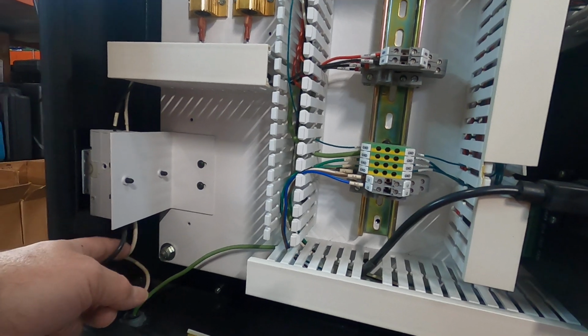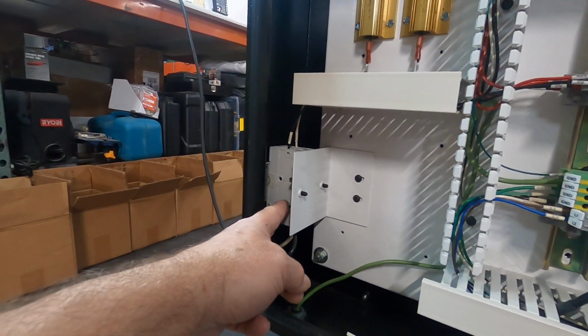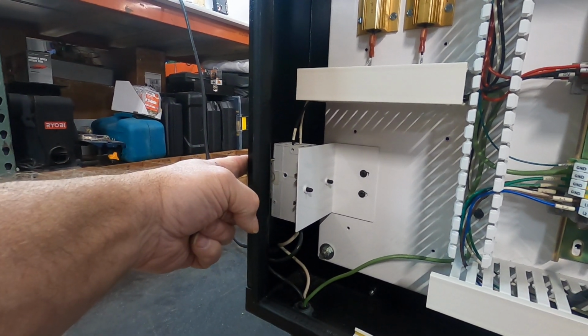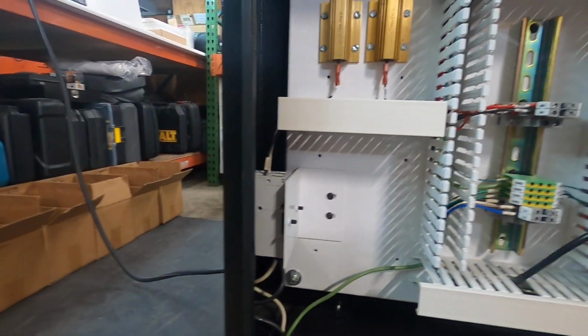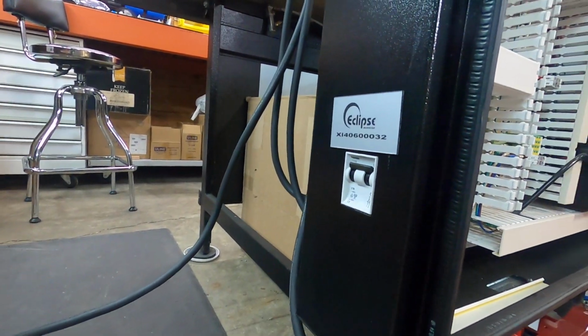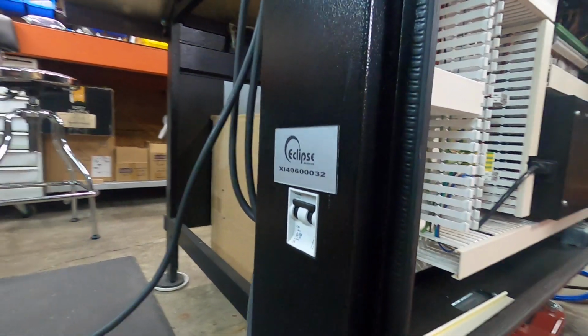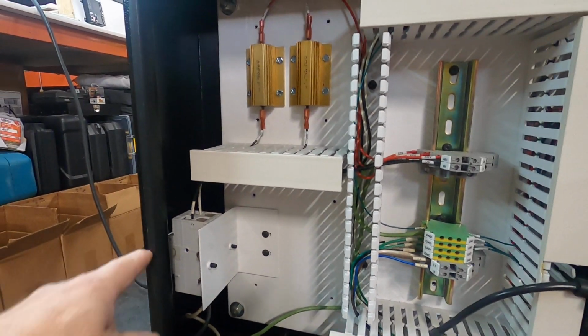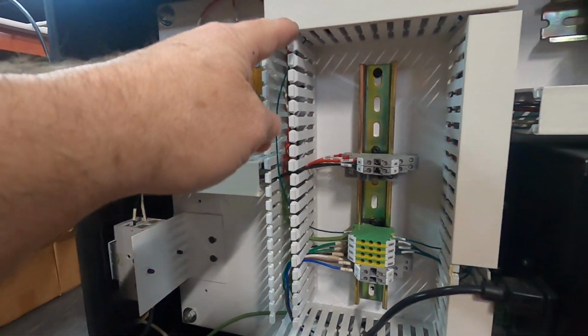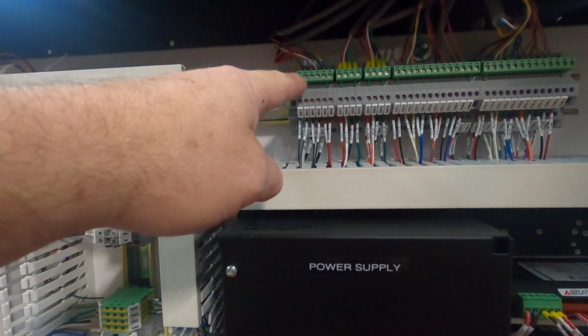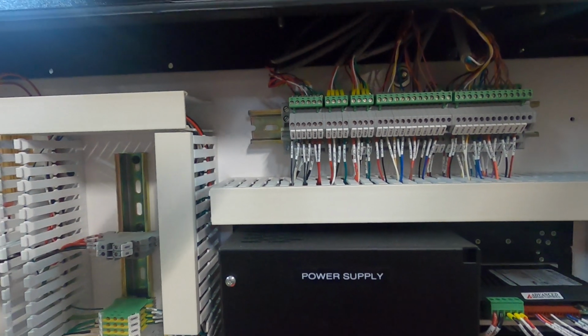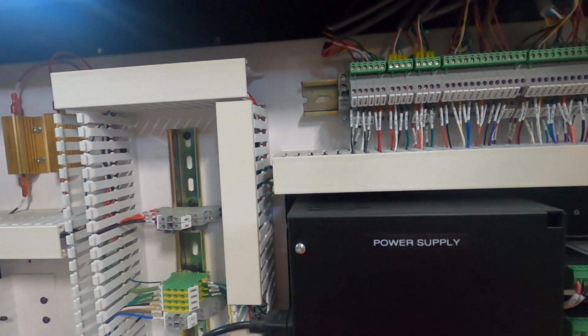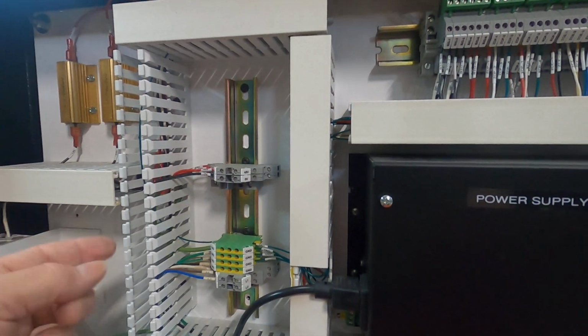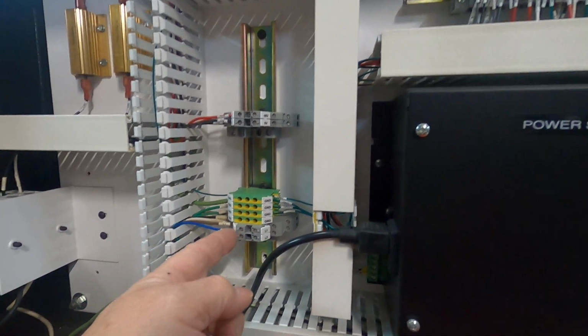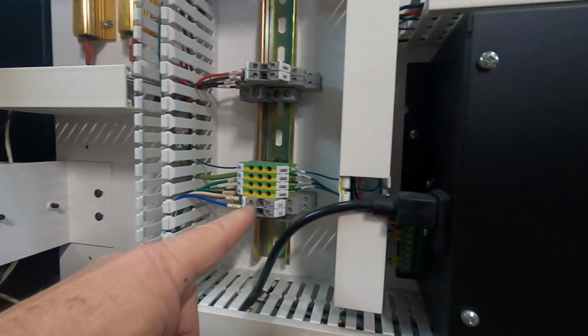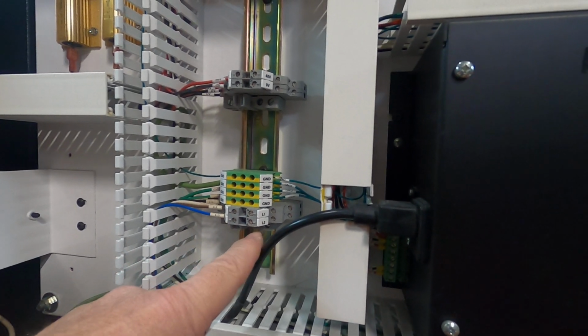The hot wire and the neutral wire, they go through this breaker, which is on the side of the machine over here. Let's see if we can get a picture of that right here. See that breaker right there with the serial number plate? Okay, it goes up here, and you can take these covers off and you can follow it, and it goes up to the power switch on your machine, and then it comes back and goes into these gray blocks right here that say L1 and L2.